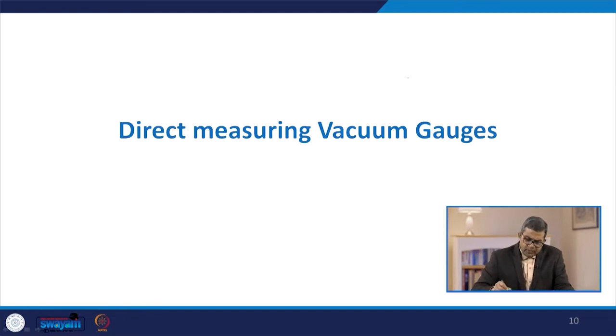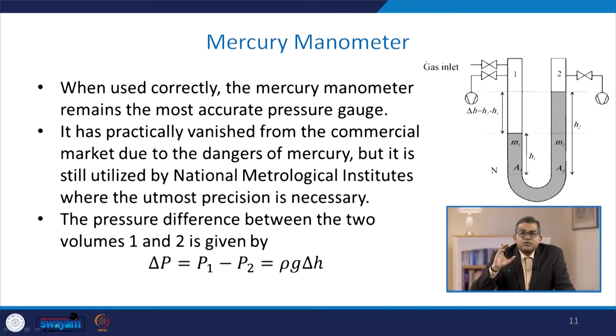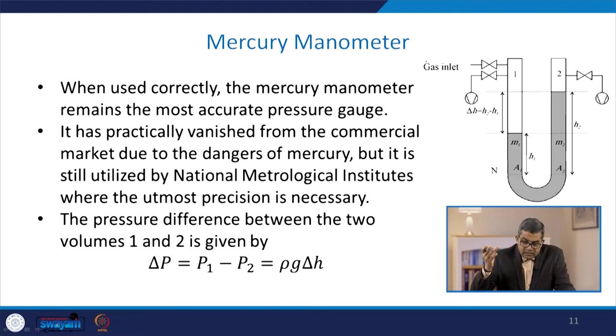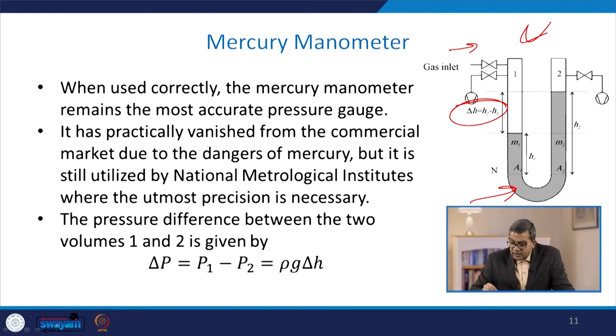Considering direct measuring vacuum gauges, the mercury manometer remains the most accurate pressure gauge when used correctly. It has practically vanished from the commercial market due to the danger of mercury, which is highly carcinogenic and hazardous, but is still utilized by national metrology institutes where utmost precision is necessary. The pressure difference between two volumes is shown by the height difference in the U-tube, with the gas under measurement connected at one end.